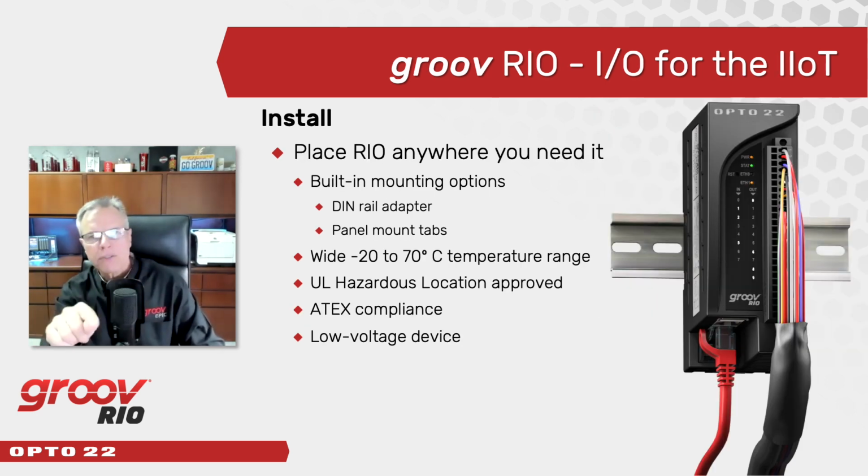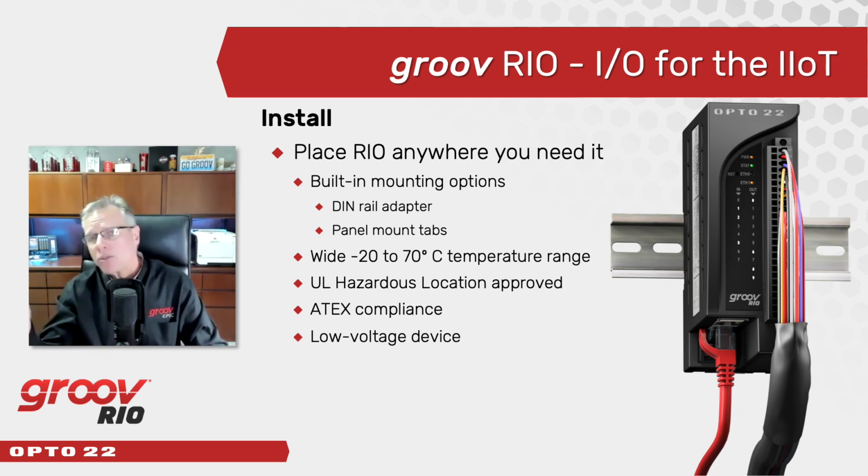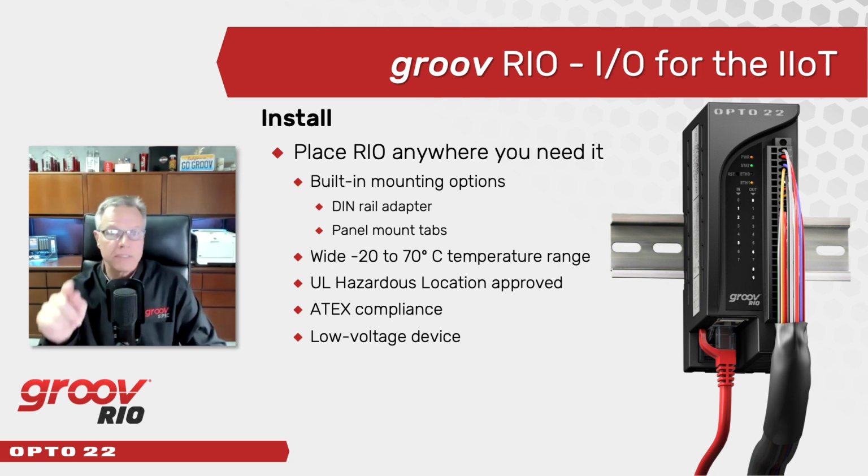Now, on to installation. Groov RIO is built to industrial standards and designed for long-lasting, reliable operation in almost any environment. Included are two mounting options, both DIN rail mounting and panel mount. Now, your choice, and they're both built in. There are no extra parts required. And with a wide operating temperature range, plus Class 1 Div 2 hazardous locations approval and ATEX compliance, you can place RIO just about anywhere.